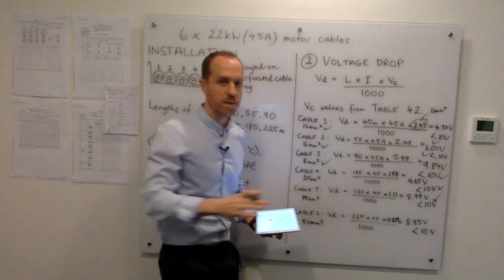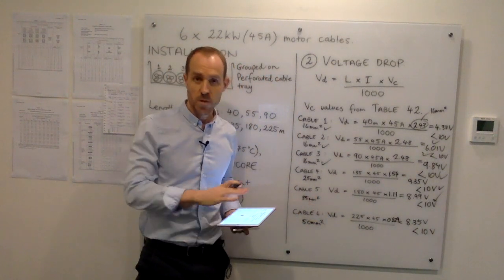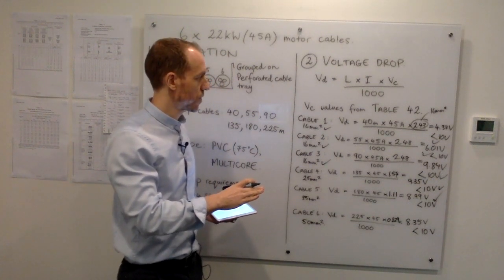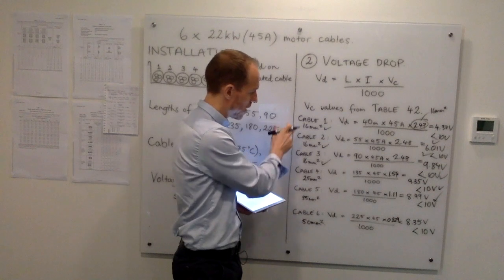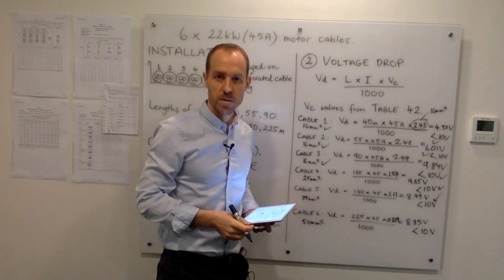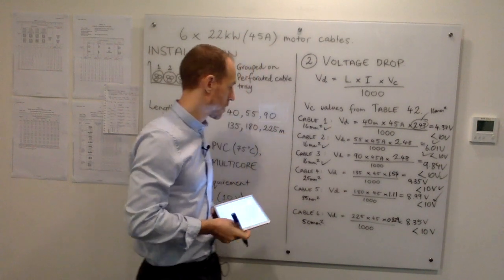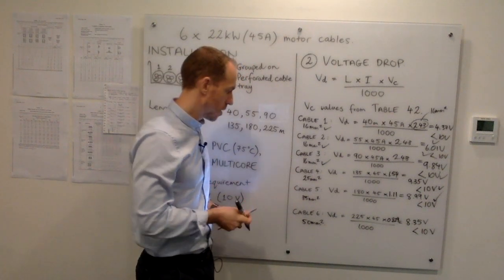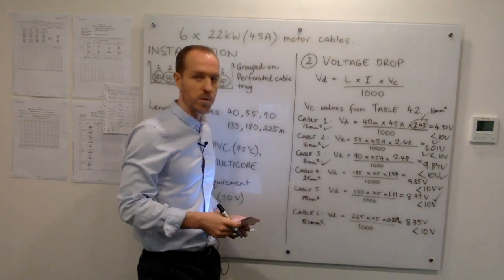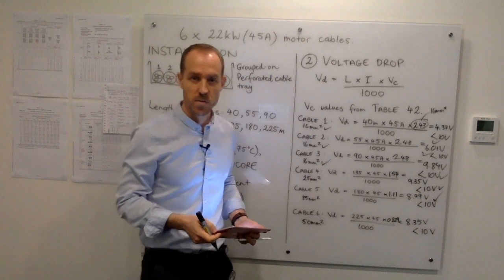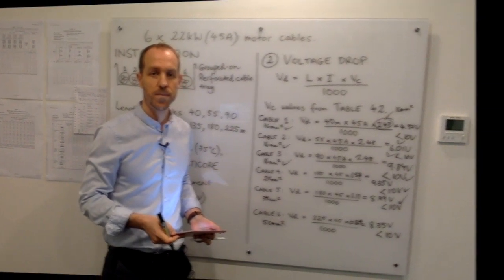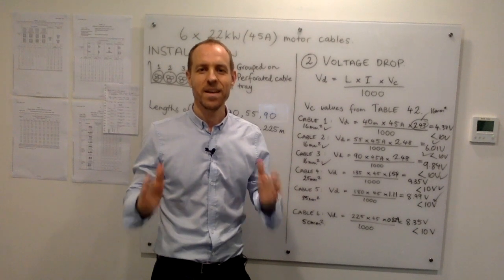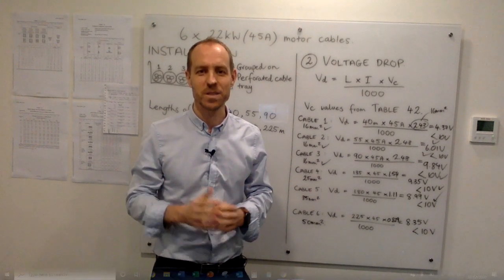8.35 volts is less than our 10 volt voltage drop requirement, so we need at least a 50mm² cable for cable 6. In summary: cables 1, 2, and 3 use 16mm²; cable 4 needs 25mm²; cable 5 needs 35mm²; and cable 6 needs at least 50mm² due to voltage drop. Now I'm going to show you how to do the same thing using software.